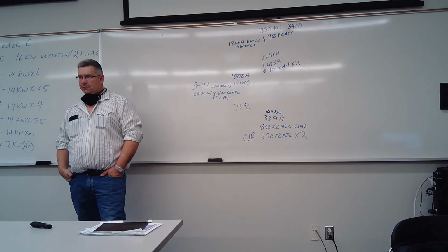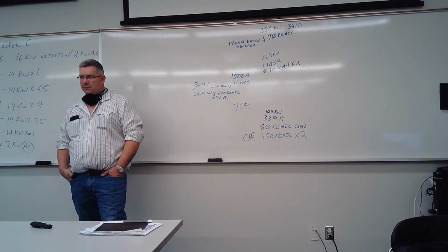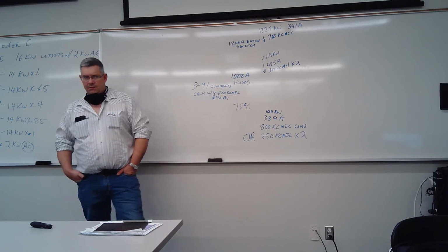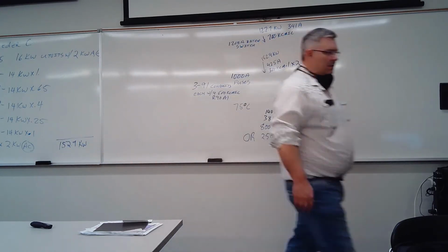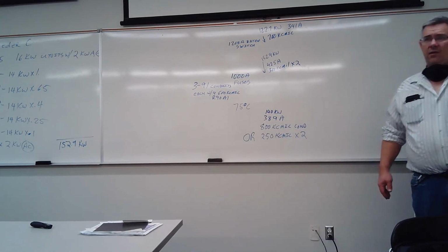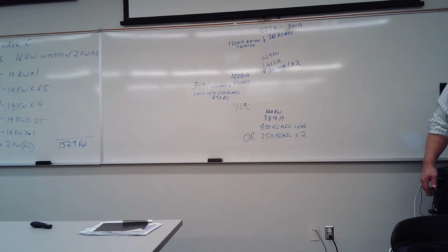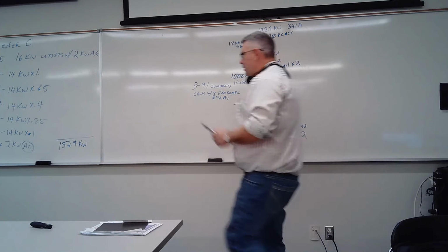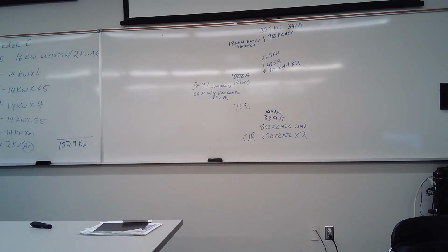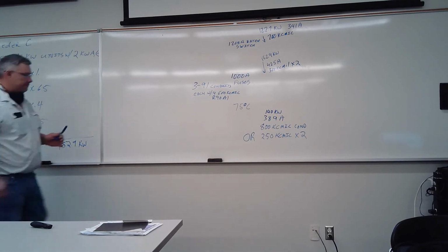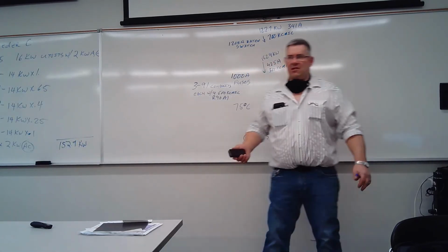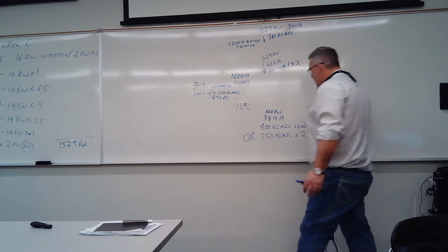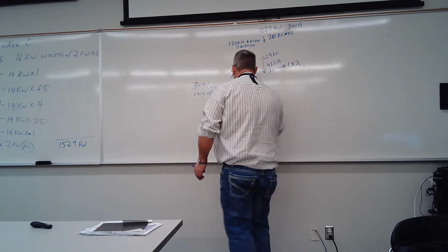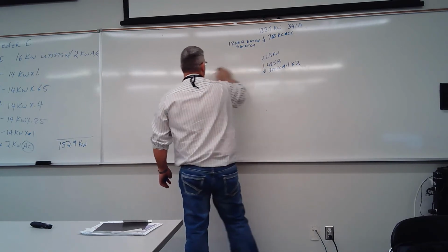But my question is, the rule says non-linear load supplied from a three-phase four-wire system, you don't count, you don't reduce. And it says, except as required otherwise by MA, demand factor 70% should be applied for everything above 200 amps. So, do you take like 550 amps and then multiply by 70%, or is there some kind of, how do you derate that? I left this out. This is kind of a neat thing. I left it out of this course because it's cumbersome. You are allowed to reduce the size of a neutral conductor. Okay?